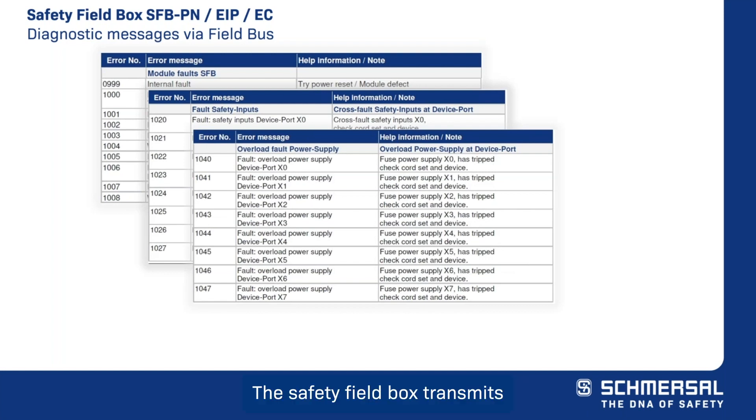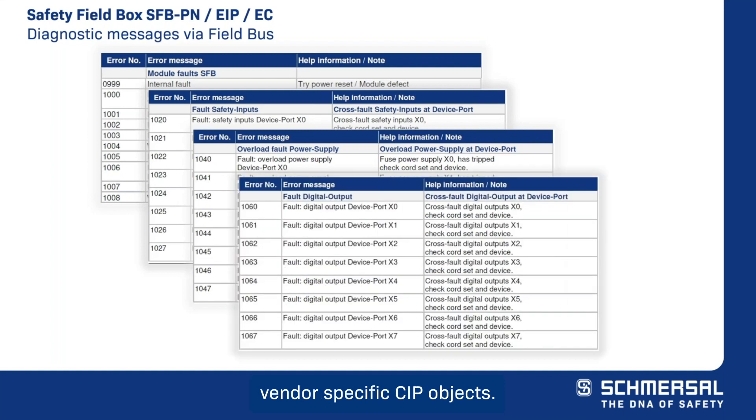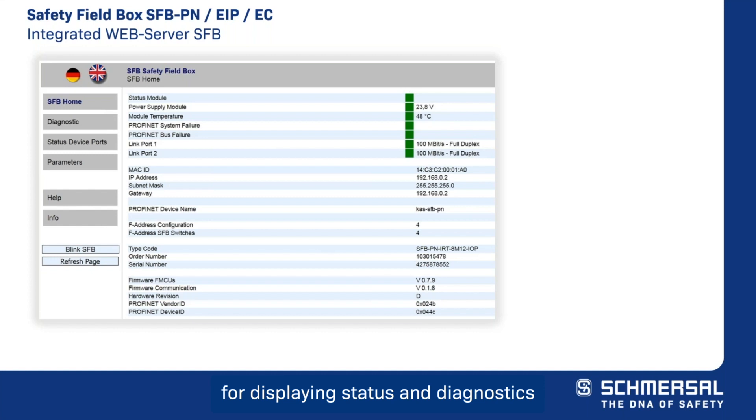The safety field box transmits all diagnostics information via vendor-specific CIP objects. These can be acyclically read by the PLC with a CIP generic message or explicit message. A web server for displaying status and diagnostics data is integrated into the safety field box. If the IP address is known, the web server can be started by entering the IP address in the address bar of an internet browser. The safety field box home page will display an overview of the most important status, network, and device data.